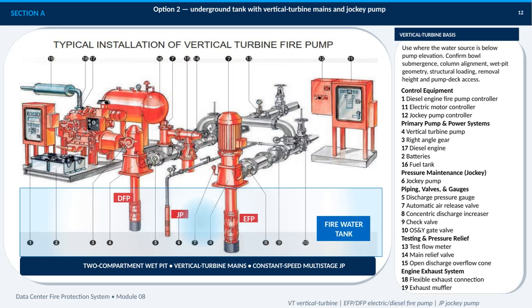This slide presents option 2. An underground tank with vertical turbine mains and a jockey pump. The arrangement uses a 2-compartment wet pit, with an electric fire pump and a diesel fire pump connected to a common fire pump discharge header. A constant speed, vertical multistage jockey pump maintains system pressure during small losses, while the main pumps provide the required fire flow capacity. The vertical turbine basis is important because this configuration is intended for a water source below the pump elevation. Before selecting it, I need to confirm several physical and structural conditions.